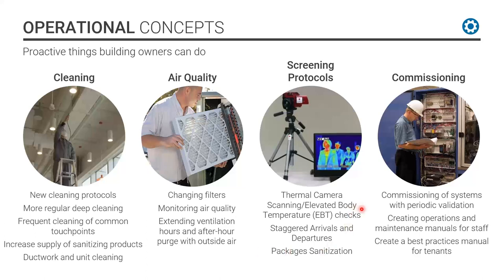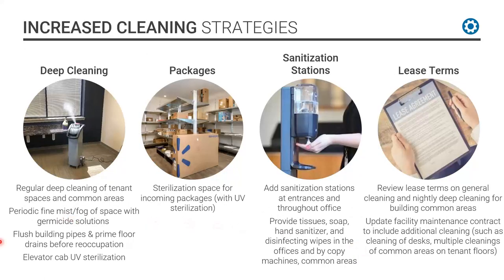What we feel very strongly about is commissioning of systems. It doesn't matter what it says in the drawings, it matters what's happening in reality. We've gone to a number of buildings, and this was last week, the outside air dampers were actually locked shut. They had never been opened. I mean, you need to check these things. Create operation and maintenance manuals for staff to check things, and then a best practice manual for occupants. If you occupy a space in the building, you want to make sure everybody else that's not in your organization operates by the same rules.